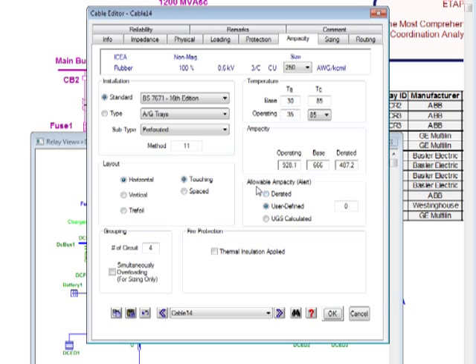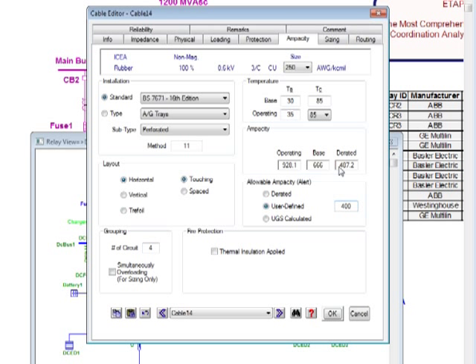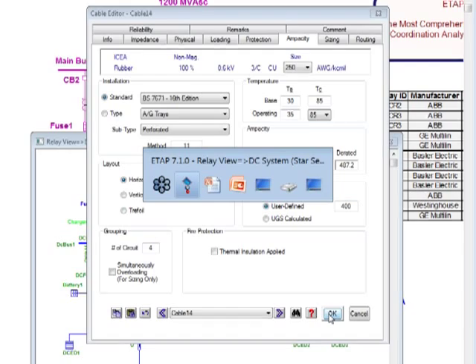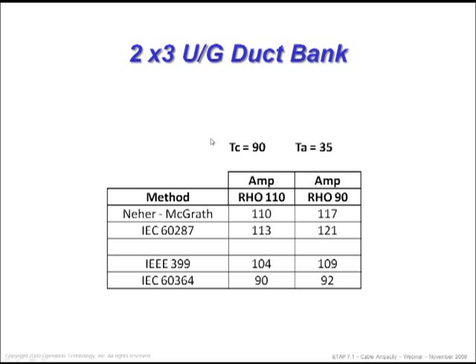Once you create the rated capacity, the program allows you to set the allowable ampacity for alerting when you run load flow. This can be based on the actual derating factor, a UGS calculation, or user-defined. Regardless, I want to put it down as 400 amps. So what I'm saying is the program allows up to 487, but when you get to 400, give me an alert — I don't want to go above 400. That's a user-defined value.